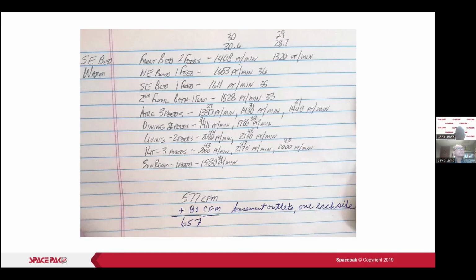All right, so feet per minute velocity: if you can only measure velocity, and your velometer doesn't measure in CFM or calculate to it, then you would use feet per minute times 0.0218. Again, that's in the handouts. You have to do this, basically. This is the only real way to find out exactly how much air you have coming out of your outlets.